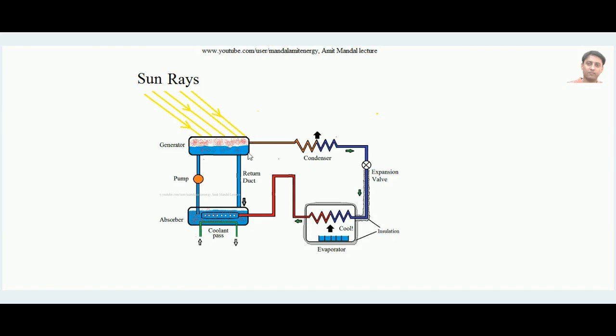In the vapor absorption cycle, heat is absorbed in the generator and removed from the absorber. That heat can be supplied to the generator by sun rays — this is exactly what the solar refrigeration system is. In the generator, instead of heat from other means, direct sun rays are made to fall on it. Concentrating collectors can focus more sun rays to supply sufficient heat and develop the required refrigeration effect in the evaporator.